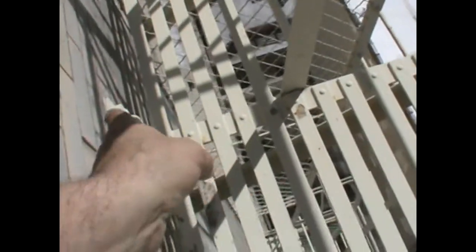Is it through bolted into the building? That appears to be the case, yeah, right there, that old square head. So that comes into the building here, and where's the plate? Can you see the plate? Not here. Okay, so who has to verify that for you? That'd be the structural third party engineer, and a lot of times they can open this up and then re-sheetrock it, but they need to verify that in 5 years. Or what can they do if they don't want to disturb this interior, and you want them to not load test this, so they can leave the original? What other options do they have?